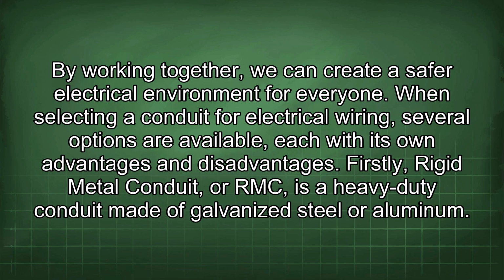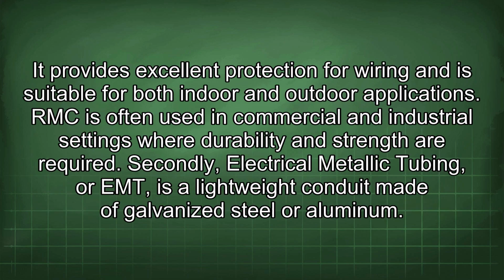When selecting a conduit for electrical wiring, several options are available, each with its own advantages and disadvantages. Firstly, rigid metal conduit, or RMC, is a heavy-duty conduit made of galvanized steel or aluminum. It provides excellent protection for wiring and is suitable for both indoor and outdoor applications. RMC is often used in commercial and industrial settings where durability and strength are required.